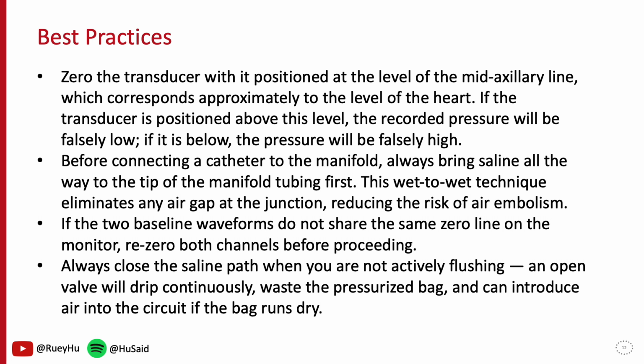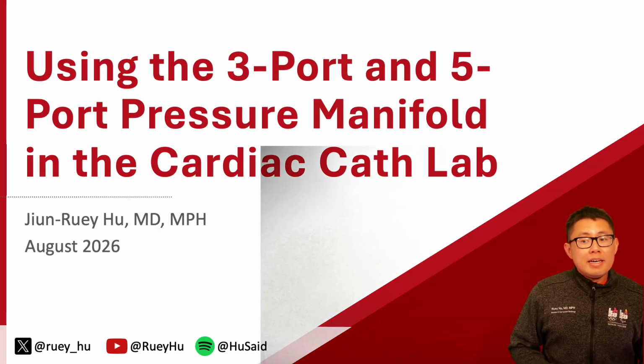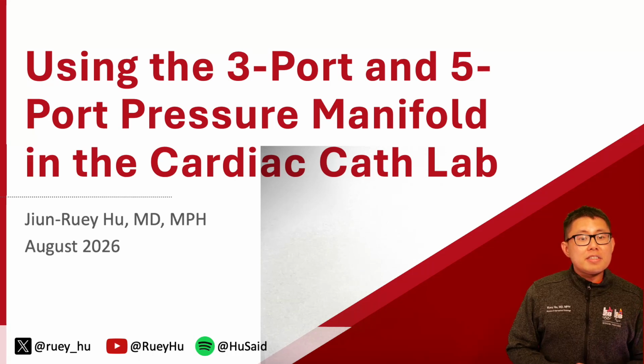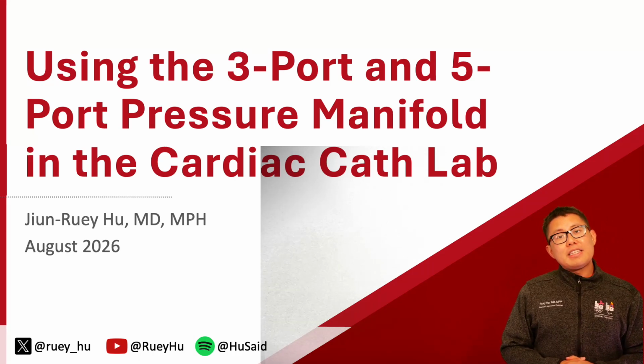Always close the saline path when you are not actively flushing. An open valve will drip continuously, waste a pressurized bag, and can introduce air into the circuit if the bag runs dry. That's all I have for you for using the 3-port and 5-port pressure manifold in the cardiac cath lab.